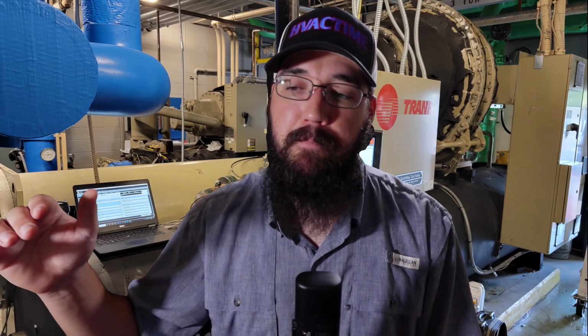Now, EXVs are implemented across everything below that too. Even a lot of the older machines that are on the market, while some of them may still have TXVs, a lot of them got converted, and we did a lot of conversions on them to EXV bodies, especially when we had systems that started having routine compressor failures due to flooding, and we had issues getting the valves to tune the way we needed. It became a pretty easy upsell to, hey, the manufacturer makes an EXV package for this. Let's just put this in. We install this, we put some sensors in here. Now we've got way more precise control over our superheat, and we can better protect your compressors in that process. And it did just that.